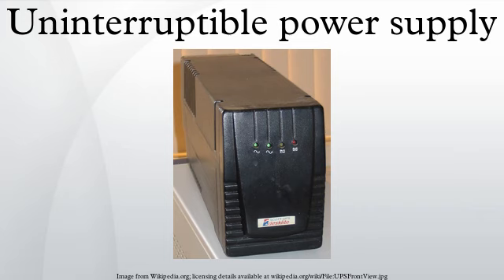The basic technology of the online UPS is the same as in a standby or line interactive UPS. However, it typically costs much more, due to it having a much greater current AC to DC battery charger rectifier, and with a rectifier and inverter designed to run continuously with improved cooling systems. It is called a double conversion UPS due to the rectifier directly driving the inverter, even when powered from normal AC current. Voltage and frequency independent.